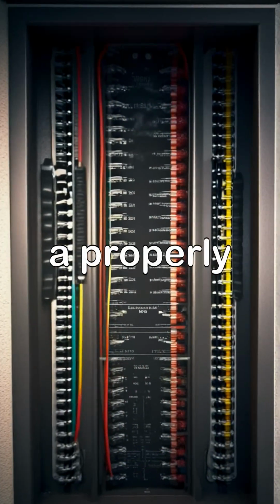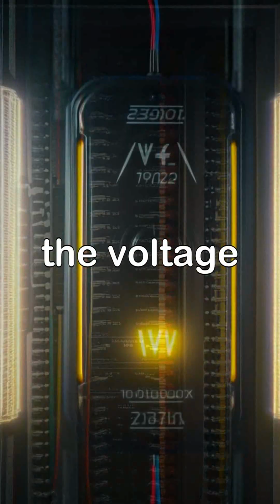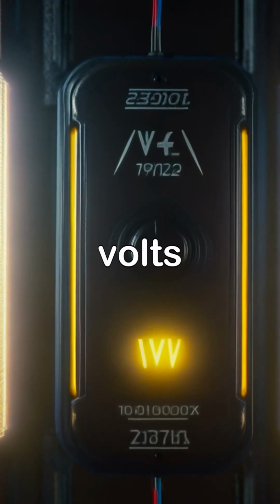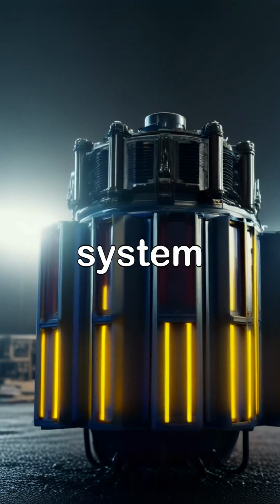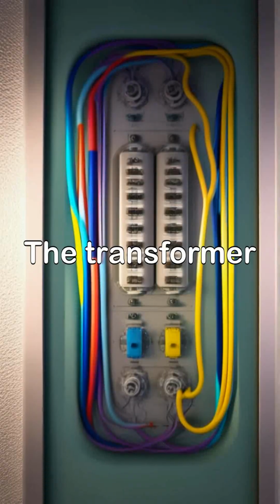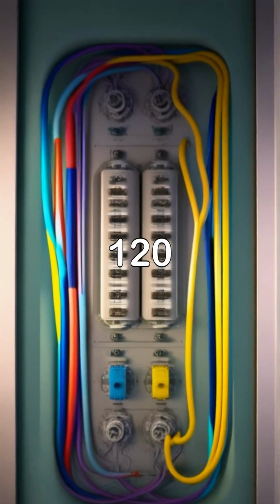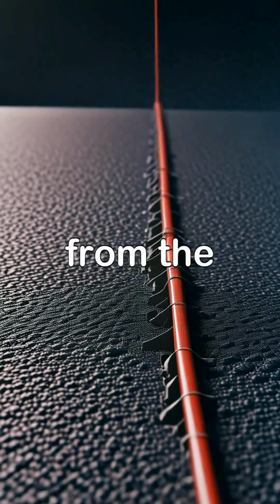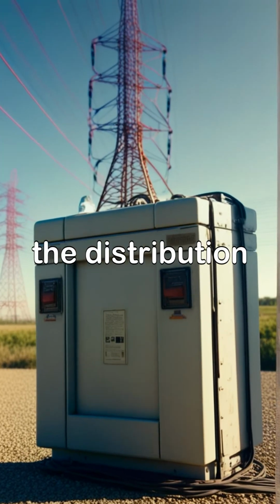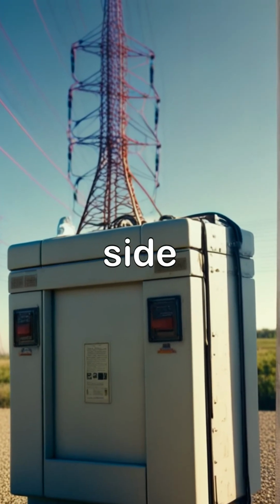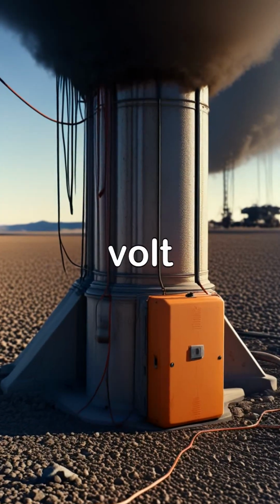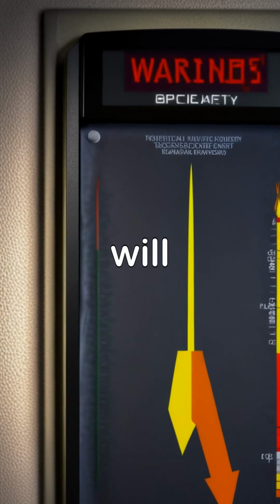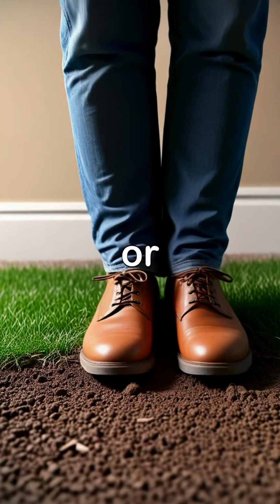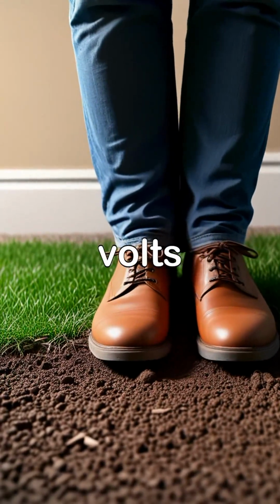One advantage of having a properly grounded neutral conductor in the house is that the voltage to ground will not exceed approximately 120 volts. Typically, voltage to ground in the electrical distribution system ranges from 2400 to 8000 volts. The transformer that reduces these high voltages to the 120 volts used in a house has a high voltage side and a secondary 120 volt side. Electric power for a home comes from the secondary side. For absolute safety, the distribution system connects the grounded conductor on the high voltage side of the transformer to the grounded conductor on the 120 volt side. So long as this connection is sound and grounded, an accidental ground on the high voltage feeding the transformer will create a fault that will trip a circuit breaker or open a fuse or otherwise turn off the high voltage and of course the 120 volts feeding the house.